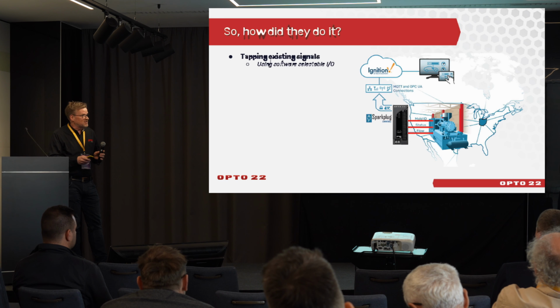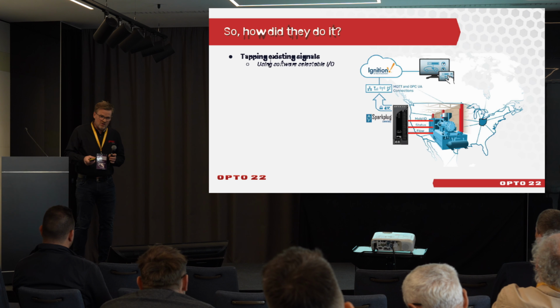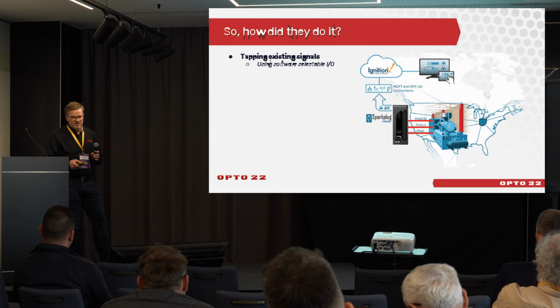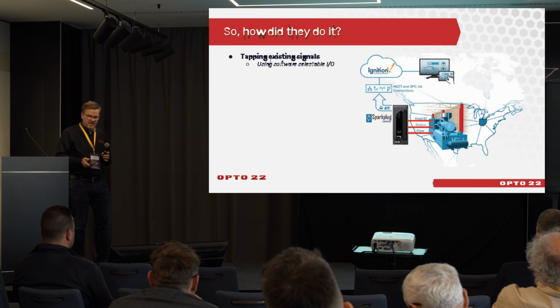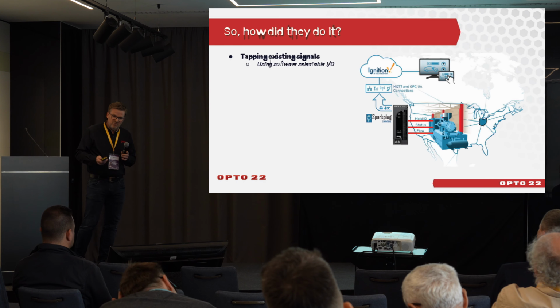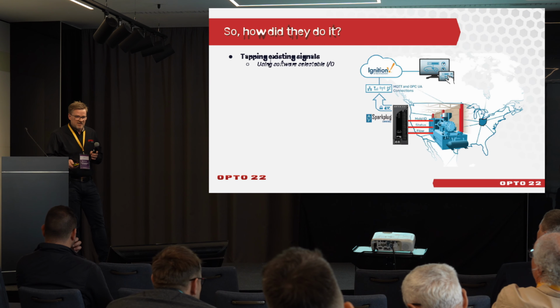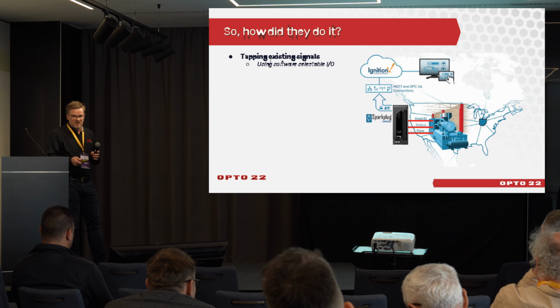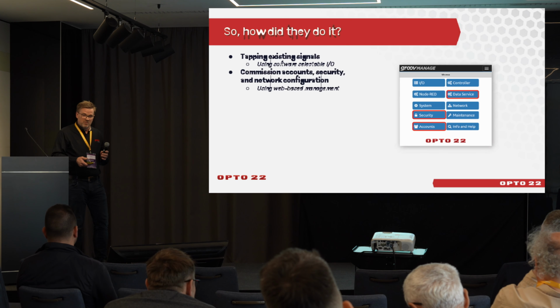This is the basic setup. Each injection molding machine has a groov RIO installed nearby, typically in the existing electrical cabinet. We're tapping into a few existing signals from the machine with configurable, software-selectable I/O that capture key metrics like mold ID, cycle status, and water flow. These critical data points are enough for MTNA to know how the machine is running.